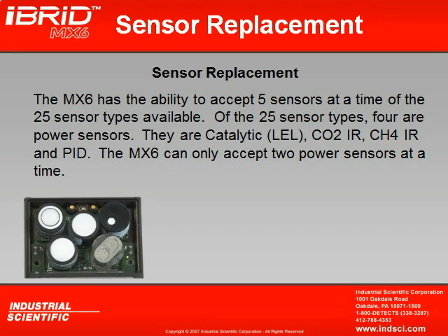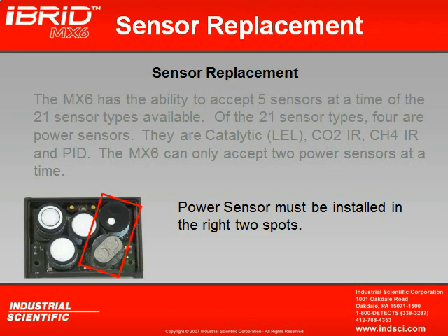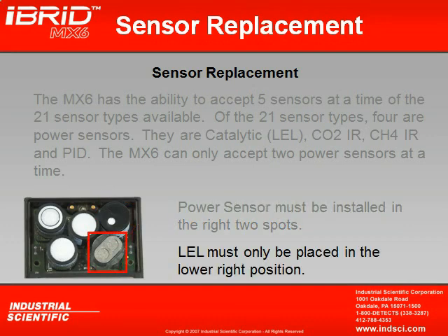We also have to ensure that when we put power sensors in the instrument, we put them in the correct spot. Power sensors can only be installed in the right-hand 2 slots. The combustible sensor must be placed in the lower right-hand position. If I put the LEL sensor in any position other than the lower right hand, or the PID not in its proper position, when I turn on the instrument it will tell me illegal configuration.